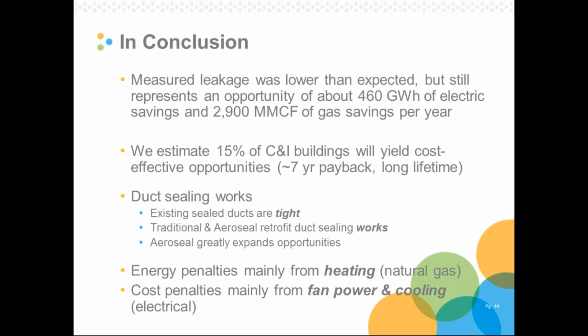We estimate that about 15% of C&I buildings will yield cost-effective opportunities, with approximately a 7-year payback. This product has a long lifetime, I would say equivalent to the duct system life. Duct sealing works. Our retrofit duct sealing worked in all cases, and the existing sealed ducts that we found were very tight. The main advantage of Aeroseal is that it greatly expands the opportunities. It really makes this retrofit market possible. Again, the energy penalties are mainly from heating in most common systems, but the cost penalties are mainly from fan power and cooling through the electrical side.